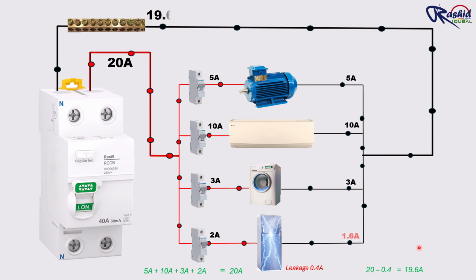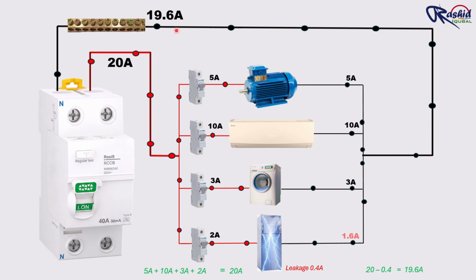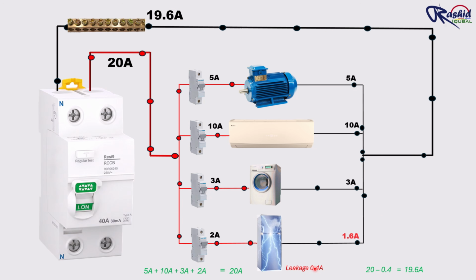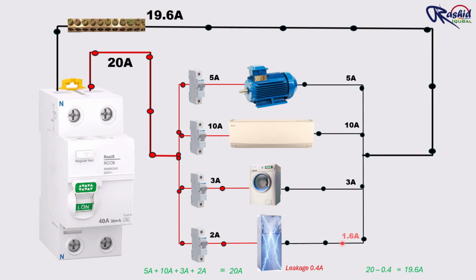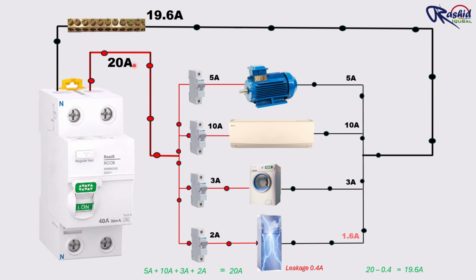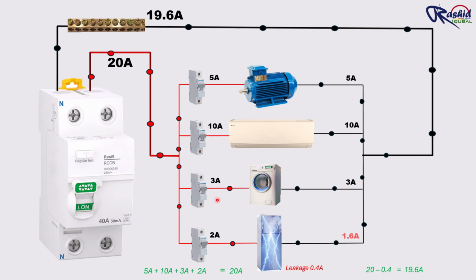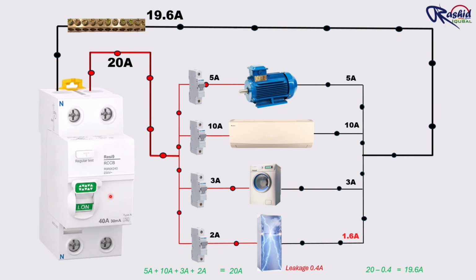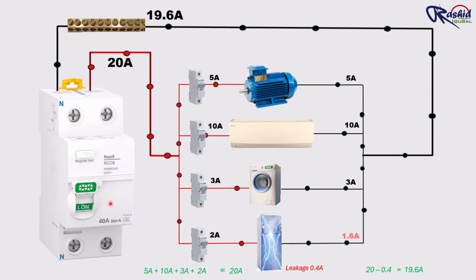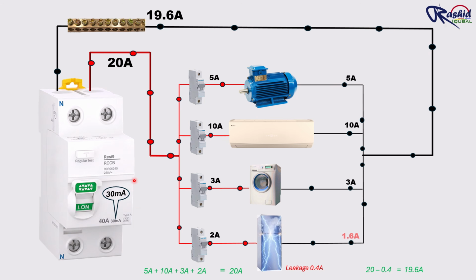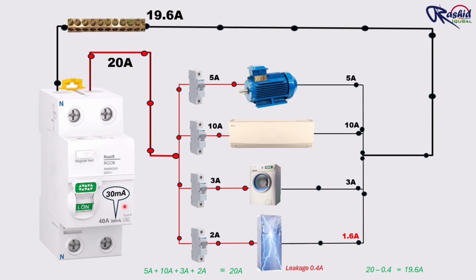So why this 19.6 ampere? Because 0.4 ampere has taken an alternate path through the earth. This difference between the outgoing phase current and the returning neutral current is called residual current, or we can say leakage current. Actually, the RCCB continuously compares these two currents. A standard RCCB used for human protection has a sensitivity of 30 milliampere, which means it can detect a leakage current as small as 0.03 ampere.